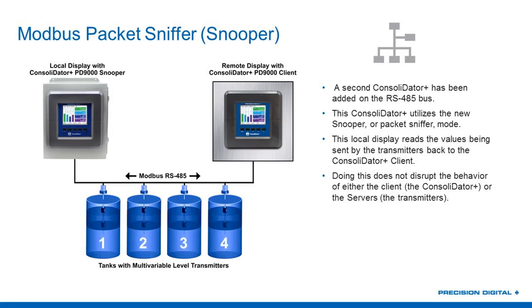Jose asks: can the display convert level to volume or mass by using a strapping table? The answer is yes — absolutely. You can do that on a 4-to-20 milliamp signal or on a Modbus input. Instead of two-point scaling, you'd use multi-point scaling and build the table right in there. That's very commonly used for people using a 4-to-20 level transmitter to show volume in a non-linear tank. With a Modbus device, you bring in the input already in feet and then scale those feet values right into volume or mass using the multi-point table.